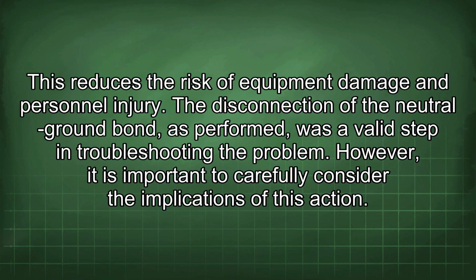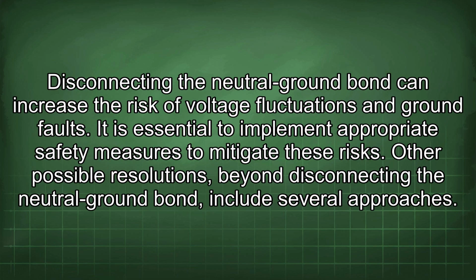The disconnection of the neutral ground bond, as performed, was a valid step in troubleshooting the problem. However, it is important to carefully consider the implications of this action. Disconnecting the neutral ground bond can increase the risk of voltage fluctuations and ground faults. It is essential to implement appropriate safety measures to mitigate these risks.